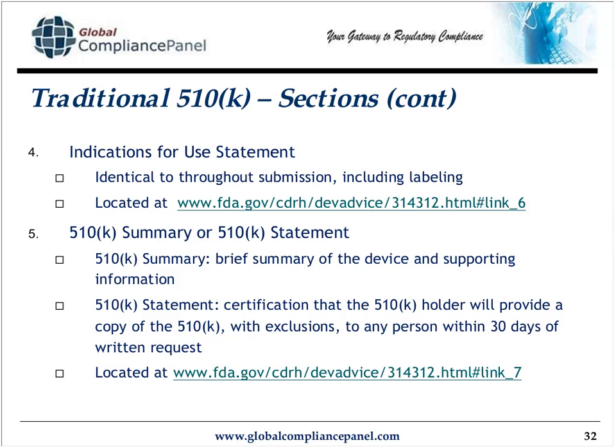The next section is either the 510K summary or the 510K statement. It is entirely up to you. Those of us who choose the 510K summary should give a brief summary of the device and the supporting information, usually a couple of pages. Those of us who feel like we want to gamble a little bit will include a 510K statement, and it's a certification, and it says, you know what, within 30 days, I'm going to submit a copy of the 510K that's redacted, of course, with proprietary information pulled out.